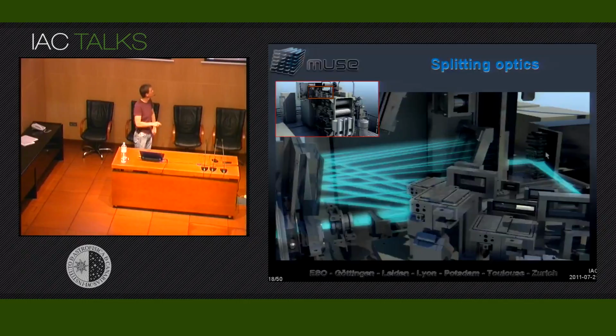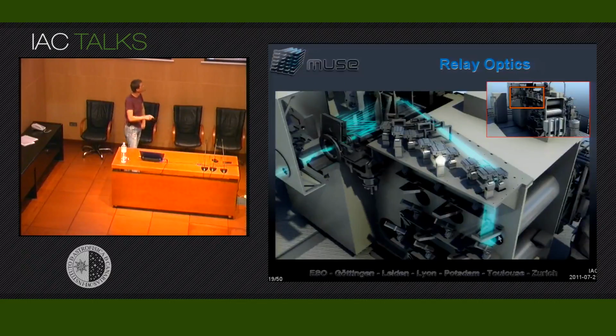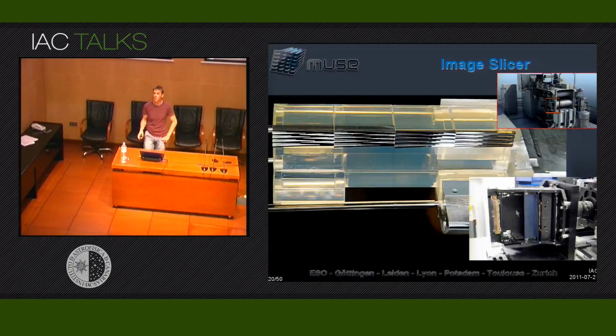So this is the field splitter. You can see these 24 mirrors that are stacked on top of each other. And so from one of these subfields, the light goes into here, into the relay optics, and then down to the respective spectrograph. Unfortunately, I don't have a rendering that shows the light inside the spectrograph, but this is what a real image slicer looks like. You can see there are 4 stacks of 12 mirrors on top of each other. And in the instrument, it sits somewhere here at one end of the spectrograph. And in reality, this is in the lab in Lyon, where you can see the image slicer here, and then the component on the other side, that's the focusing mirror array, which then sends the light into the spectrograph to be dispersed.